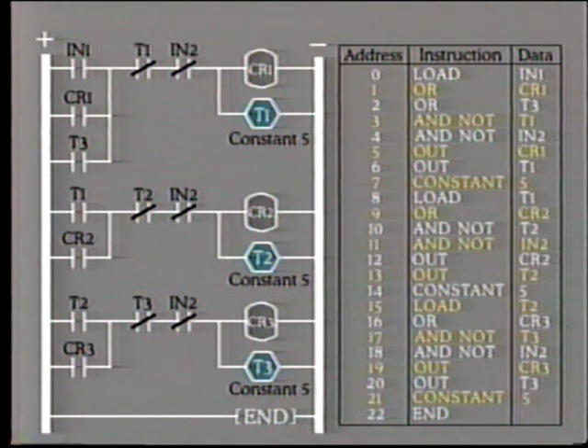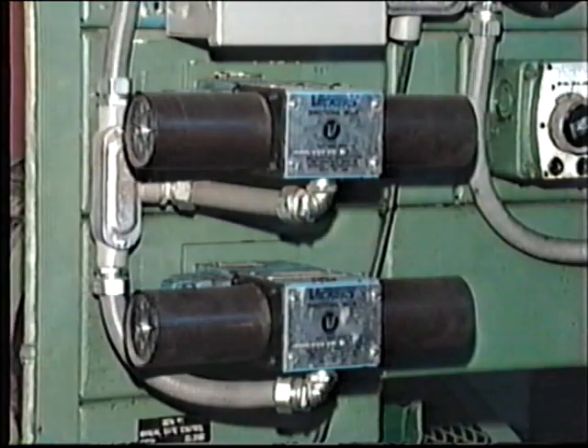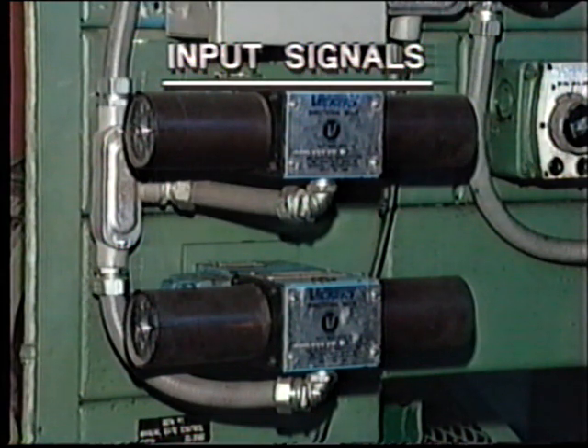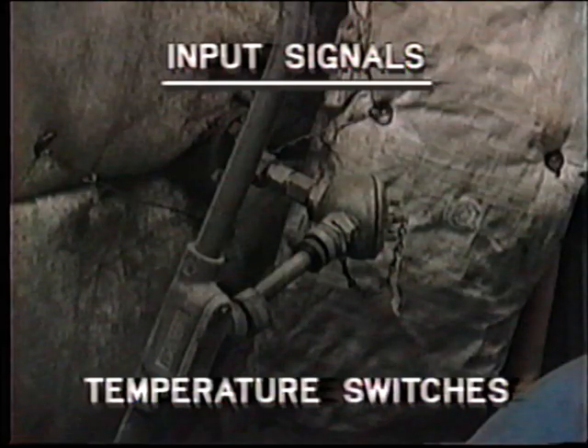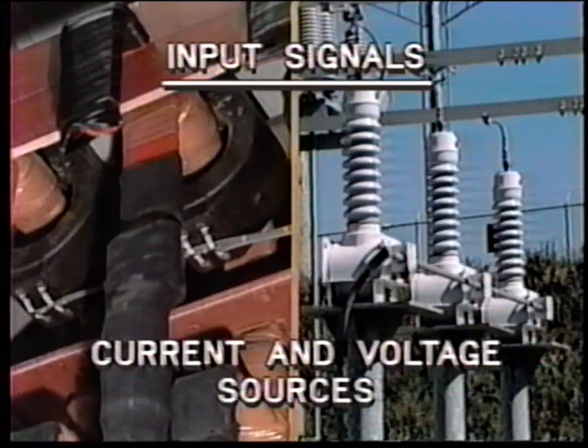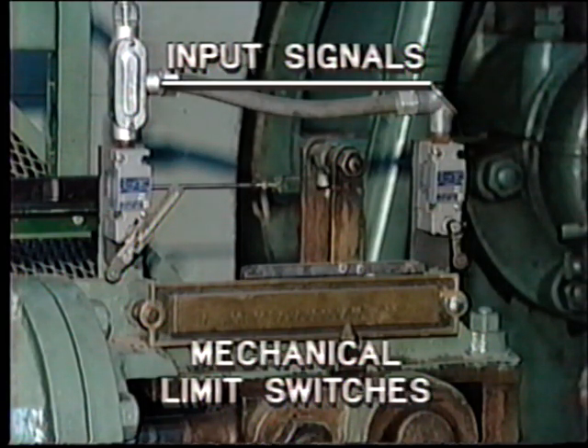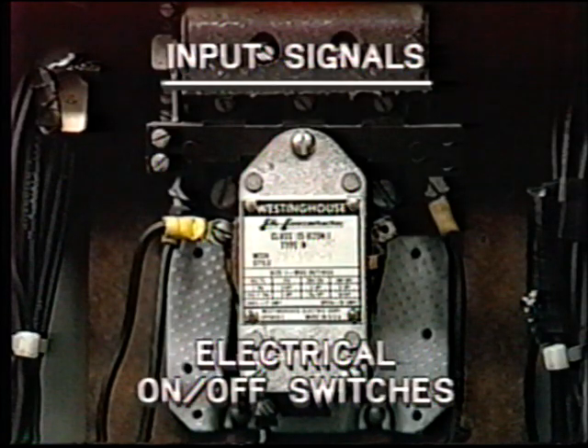Logic can also be presented by the electrical control diagram. This is known as ladder logic for obvious reasons. To work out the sequence of actions, we start at the top rung, left to right, and work our way down to the bottom. The top rung will usually initiate action on the second rung, and so on, all the way down. In the solid wired scheme, all of these contacts represent relays, and these are connected to various input and output devices. Input signals to the control scheme are fed from such devices as pressure switches, temperature switches, current and voltage sources, mechanical position switches such as travel limit switches, electrical on-off switches, and so on.